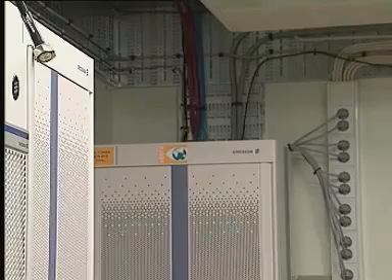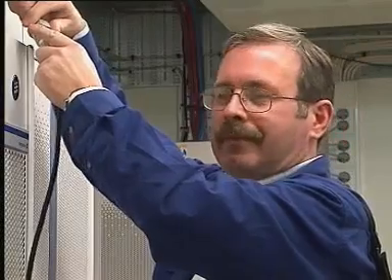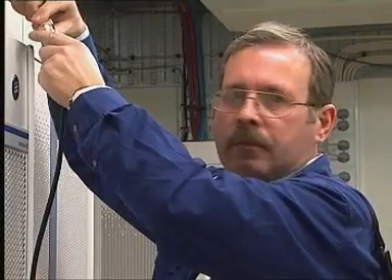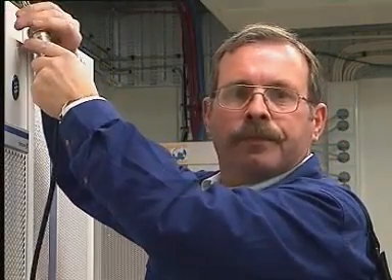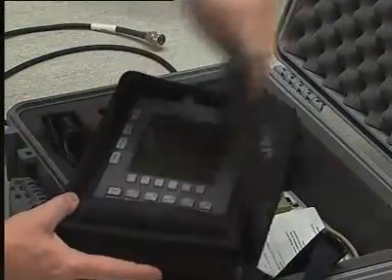Before any tests are made, we should have completed the frequency and calibration stages. Have we not calibrated it? Then we must take the time to calibrate it before we can use it. Whenever the Site Master is first switched on, it must be left for a few minutes to warm up and stabilise.